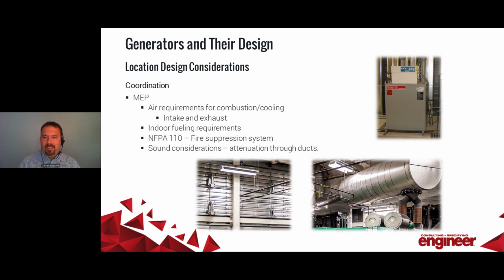It's surprising how large that duct ends up getting for the exhaust if you go multiple floors up as you get back pressure on that shaft. I'm not a mechanical engineer, but I know enough to know that that can get somewhat complicated. Again, the indoor fuel requirements. Do you have a day tank in the room? Where's the main tank? Is it buried in the grade outside? There's fuel transfer pumps. There's a lot of requirements that go with a generator that are mechanically related.